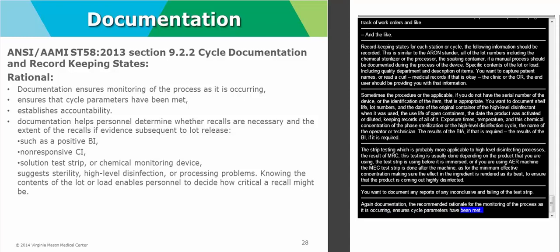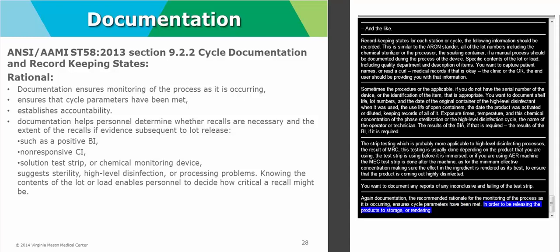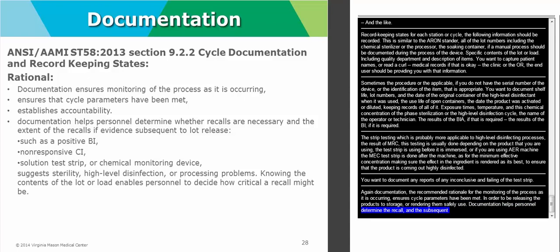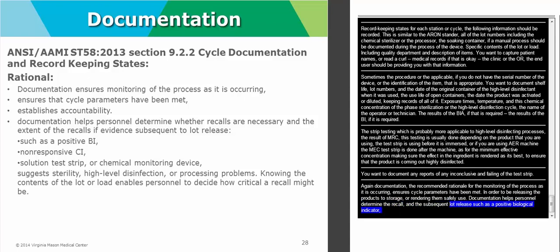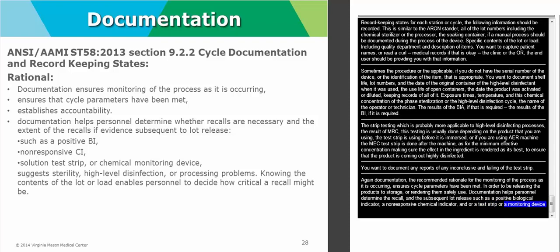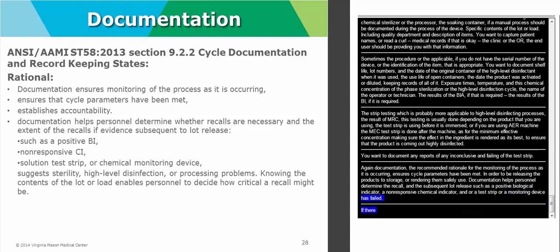And it establishes accountability. Documentation helps personnel to determine whether recalls are necessary and the extent of the recalls if there is evidence from the subsequent lot release, such as a positive biological indicator, a non-responsive chemical indicator, or if a solution test strip or chemical monitoring device has failed, or suggests that there were processing problems with sterility or high-level disinfection. Knowing the contents of the lot or the load enables personnel to decide how critical a recall might be.